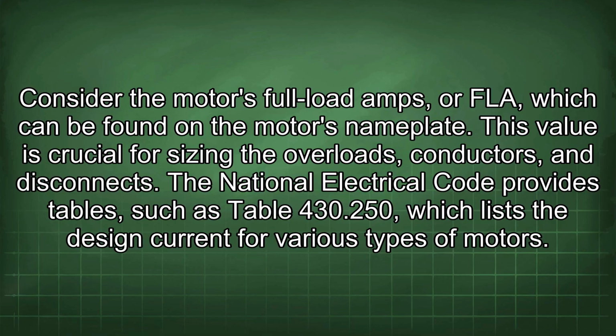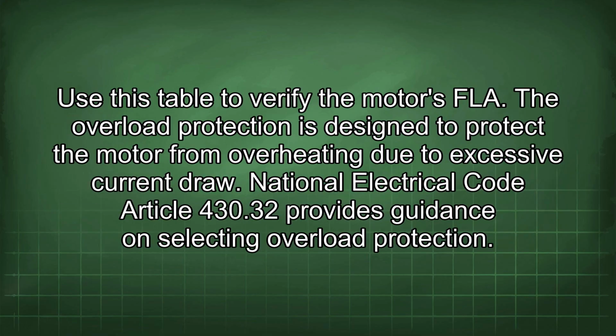The National Electrical Code provides tables such as Table 430.250, which lists the design current for various types of motors. Use this table to verify the motor's FLA.